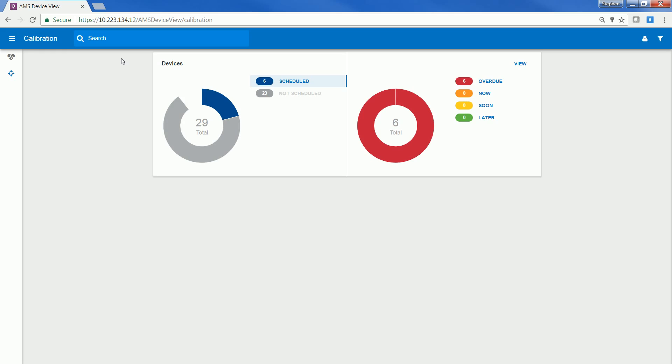AMS Device View can also be used for calibration. You can see whether a device is scheduled or not scheduled for calibration. You also can see the time frame. Whether the device is overdue, needs to be calibrated now, which means this week, soon, which means this month, or later, which means more than a month.